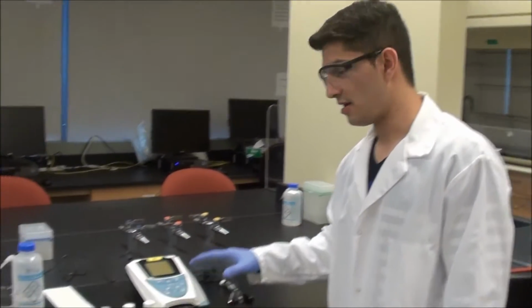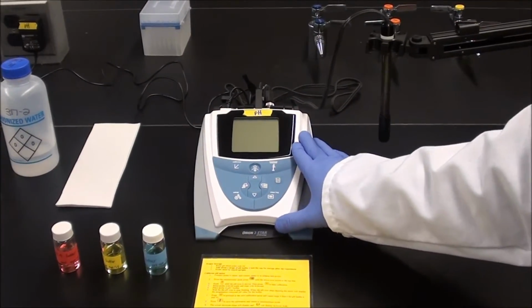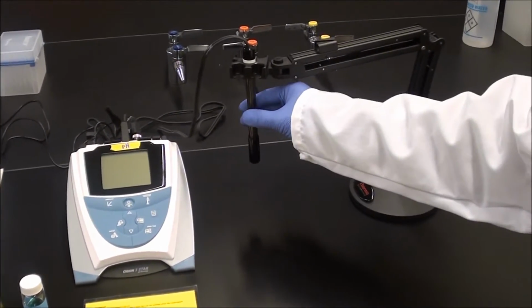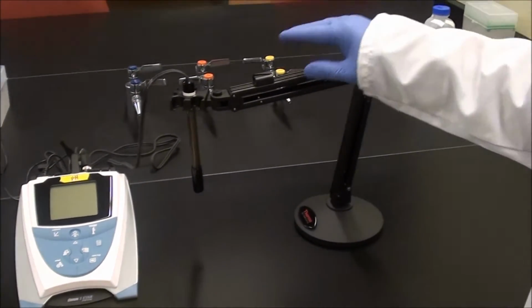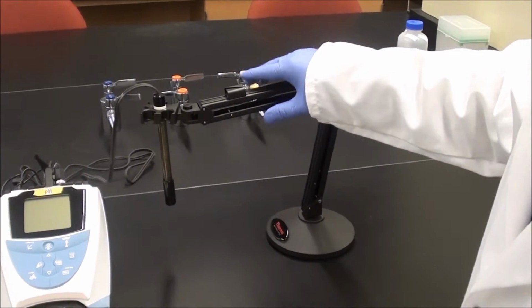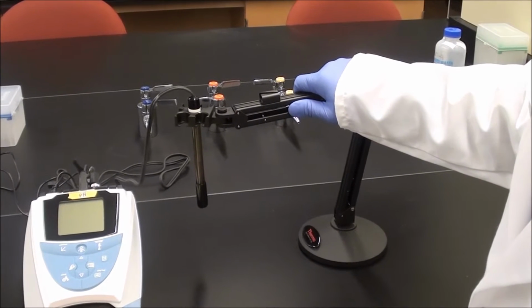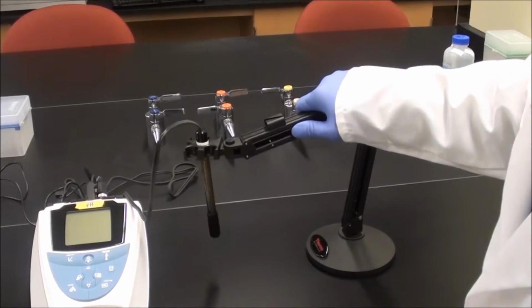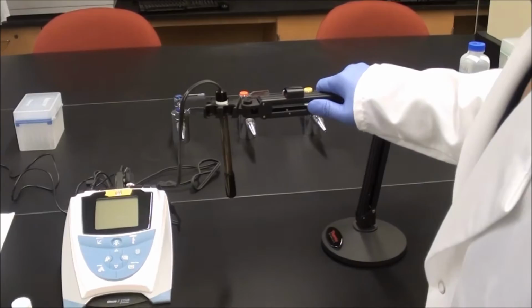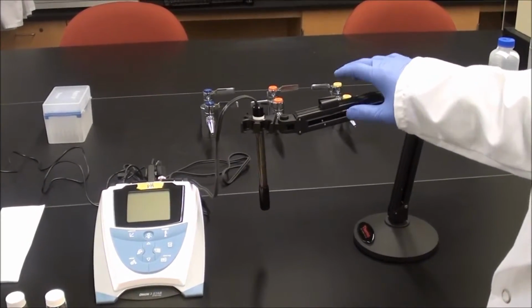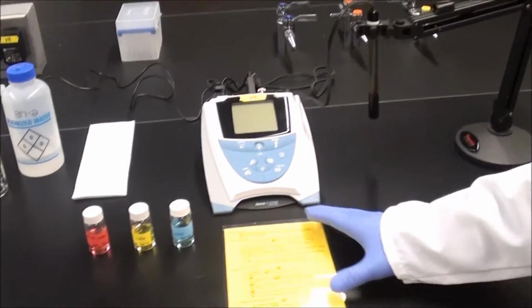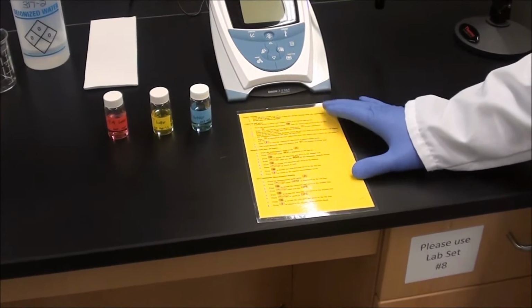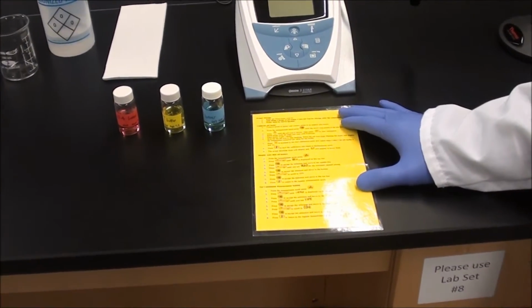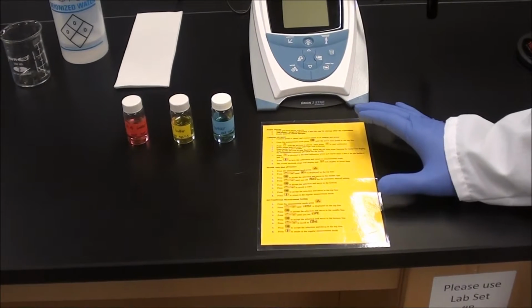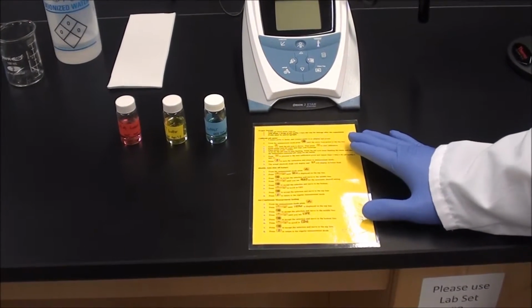So to start off, the materials we're gonna need are a pH meter and the pH electrode or the pH probe. I'll be using this arm because it gives me a really smooth up and down movement, since the probe must be stored upright during the measurements. We're going to need a manual that shows the instructions on how to calibrate a pH meter, and it might be different for different pH meters, so make sure that you use the right one.